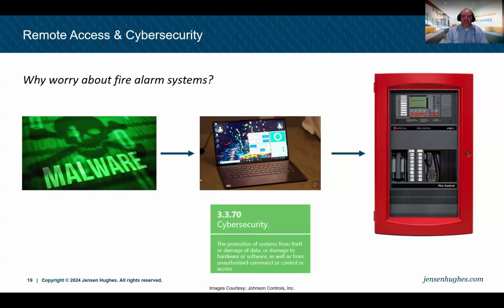All of those concerns now are built into NFPA 72 under the cybersecurity rules. The cybersecurity rules in the 2022 edition of NFPA 72 are very brief. They come with a lot of recommendations. But the 2025 edition of NFPA 72, which just hit the street, and some jurisdictions will be accepting as early as January 1st, 2025, has a litany of rules in Chapter 11, which is now the cybersecurity chapter. So I wanted you to be aware that this is all very new to the fire alarm industry, but anytime we have our fire alarm systems connected to anything remote, cybersecurity is going to become front and center, something we have to consider for the safety of our fire systems.